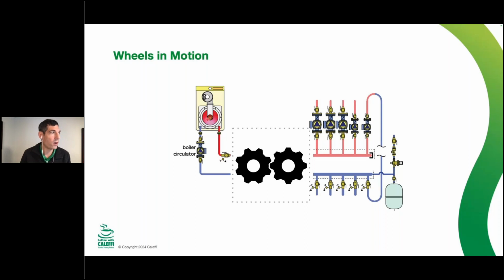So the gears in conflict here is one way to think of a system that has two customers that we're trying to address at the same time. This customer needs X number of GPM. This customer needs Y number of GPM, or if it's a variable speed or multi-zone system, this could be any number of gallons per minute. If this is a variable speed pump, it could be 1 GPM, it could be 100 GPM, depending on the system. So we don't want that going through our ModCon boiler or through a heat pump or something like that.